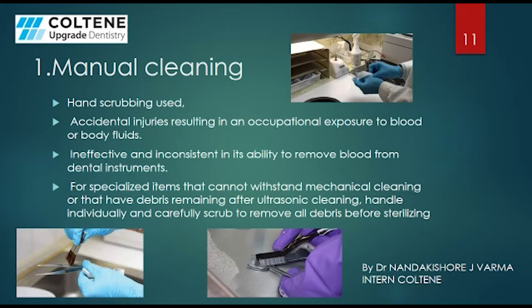The major disadvantage, or rather the major problem we have all faced, is accidental injuries, especially needle pricks and sharp instrument pricks. It's also not 100% efficient, because we are all human. We cannot clean each and every instrument or give our 100% every time, or clean every nook and corner of the instrument. For some specialized instruments which cannot withstand mechanical cleaning, we use manual cleaning after the ultrasonic cleaners have been used, to make sure that they are 100% clean.